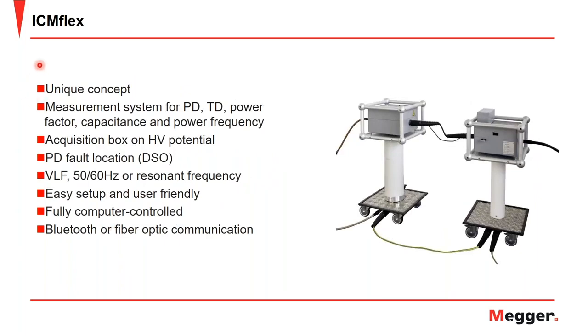Next, we have the ICM Flex, which is a unique concept, where the measurement system is capable of partial discharge, tan delta, power factor, capacitance, and power frequency measurements, where the acquisition is actually located on the high voltage potential, is capable of PD fault location with the DSO option, is capable of being used with multiple types of sources such as VLF, power frequency, or resonant frequency sources, is easy to set up and user-friendly, is fully computer controlled, and is capable of Bluetooth or fiber optic communication for noisy environments.